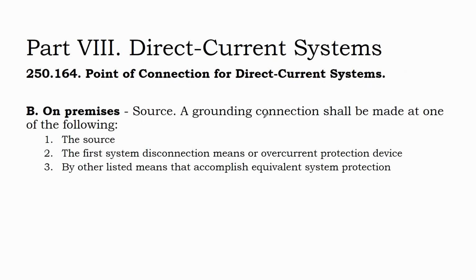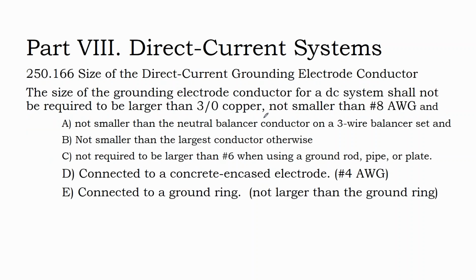Okay, so on premises, a grounding connection shall be made at the source, the first system disconnecting means, or by other listed means that accomplish equivalent system protection. And so you have listed ground fault protection systems that are not positively grounded that still get the job done nowadays. When we're sizing the DC grounding electrode conductor, where is our DC electrode conductor showing up? Well, up on the rooftop where the system is exposed to metal parts, there's no AC equipment up there. Technically that metal racking can be exposed to DC current. You need to connect it to the DC grounding electrode system.